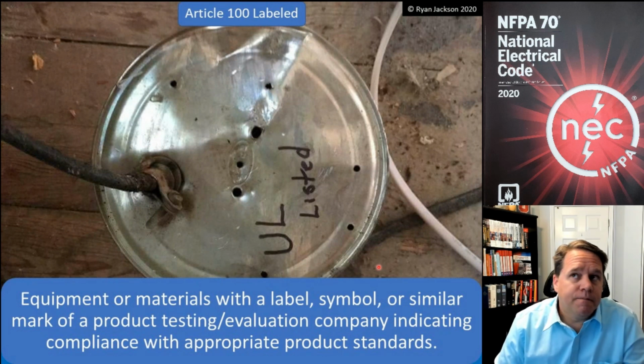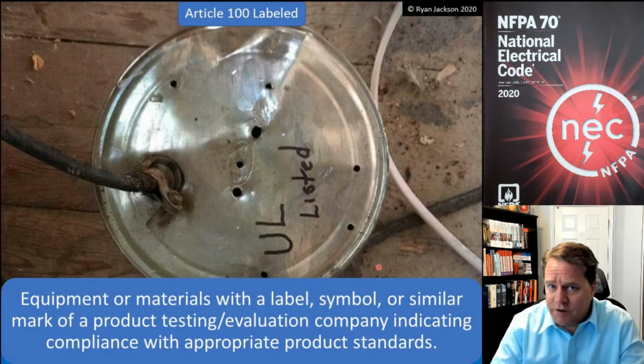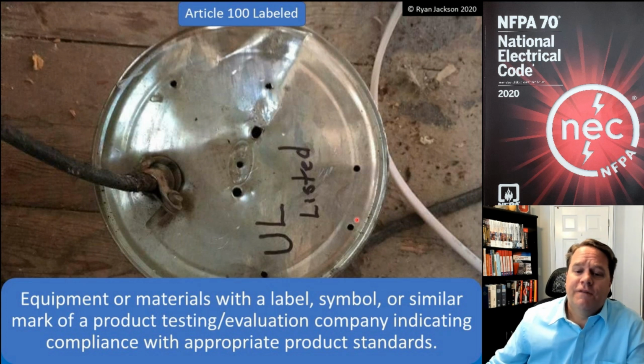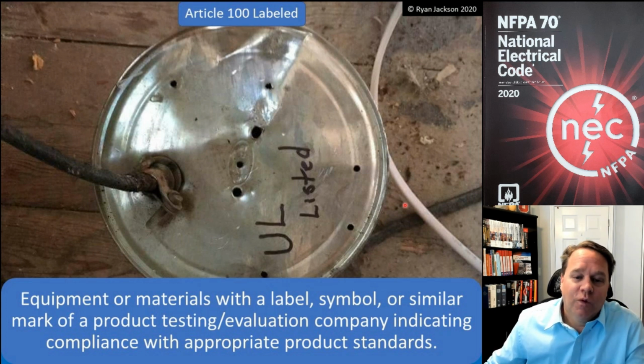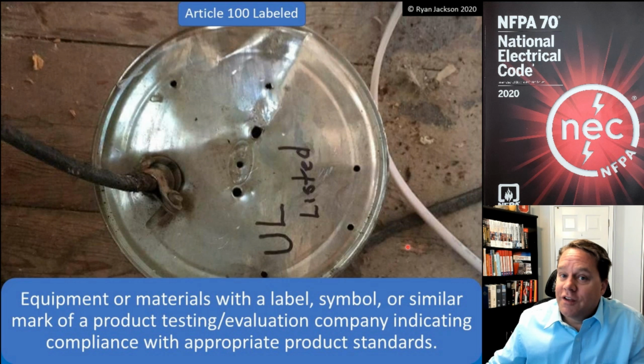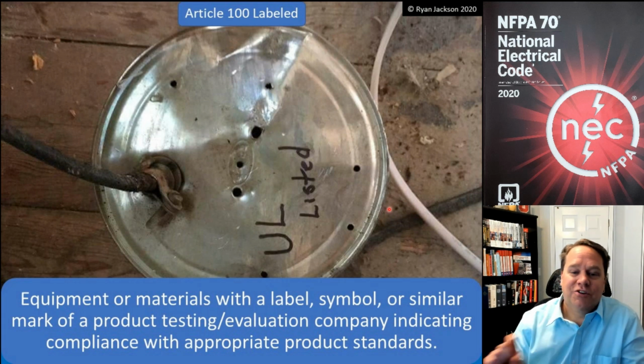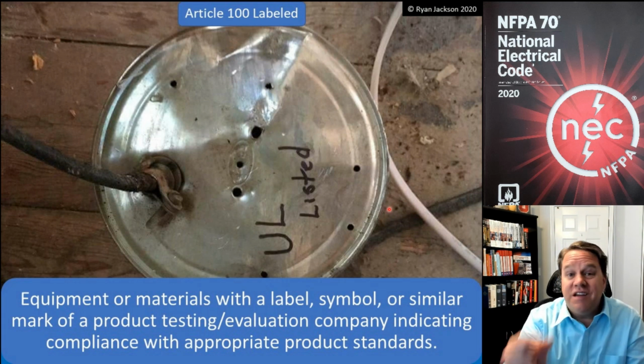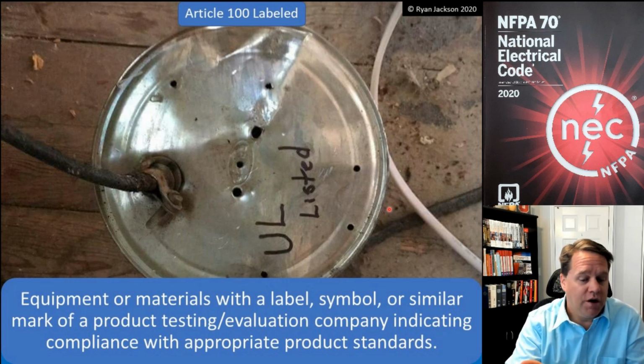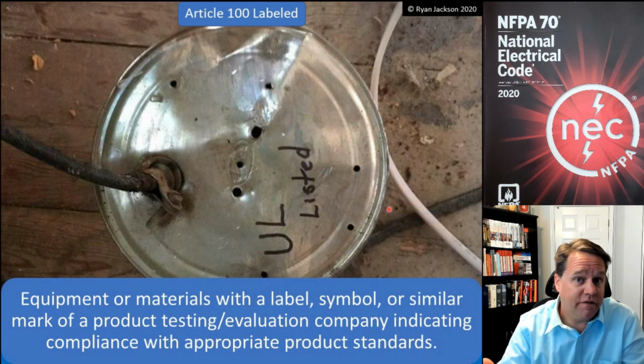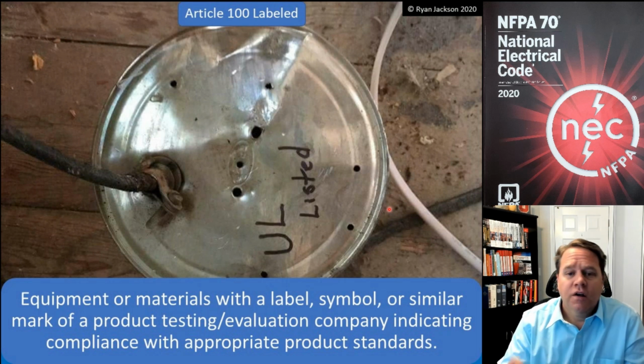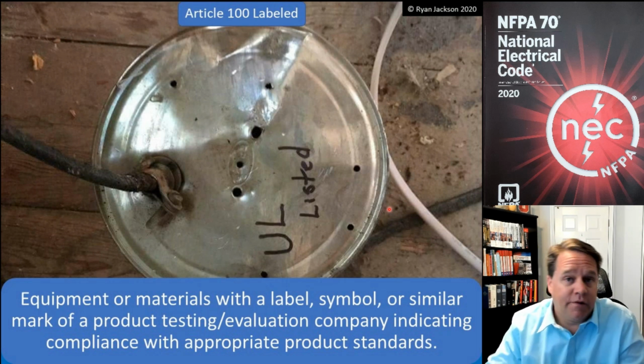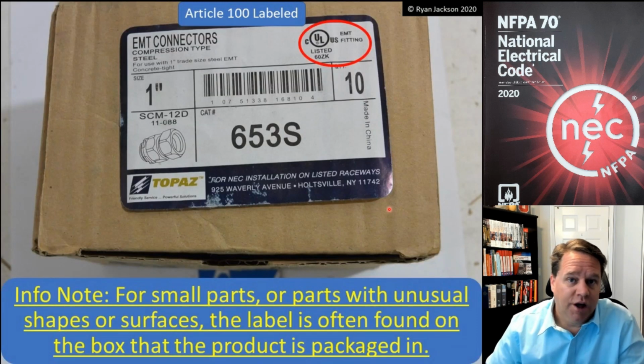It's worth remembering what the product labels look like. If you just see UL listed with a Sharpie, that's probably not a listed product, so we want to make sure we know what the UL mark is, what the ETL mark is, the Intertek mark, and the FM labs, especially if you're doing hazardous locations. They do a lot of hazardous locations testing. So all of the different testing laboratories have different marks, and we do need to familiarize ourselves with what those marks look like.